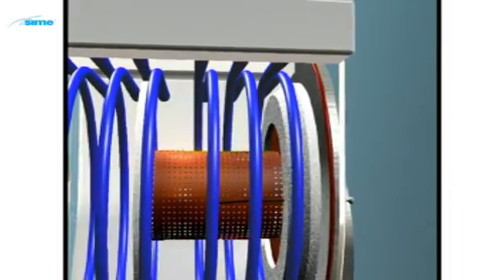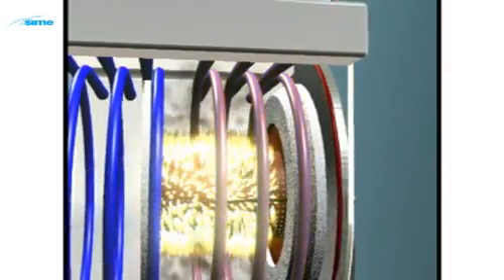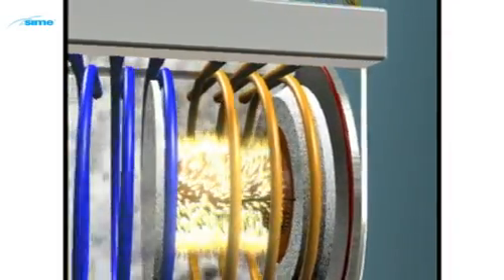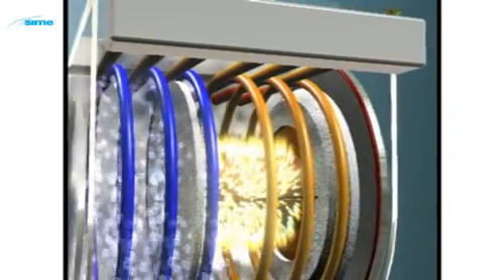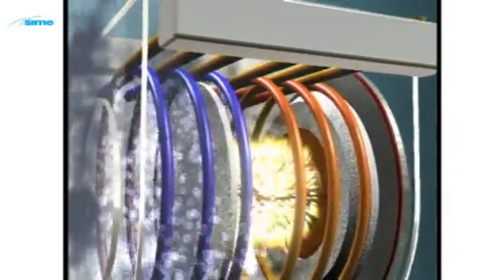The gas mixture is ignited around the 360 degree burner. The front section of the heat exchanger is heated by the primary heat, and the unused heat passes through the coils into the jacket.